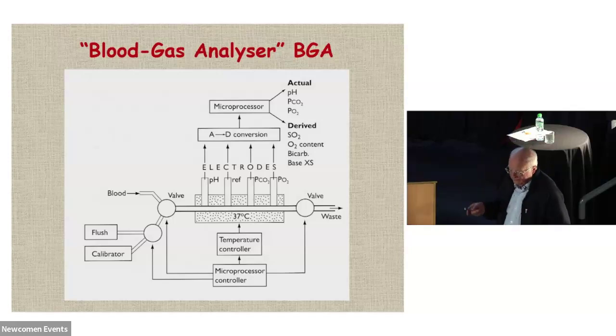So now moving from the gases to looking at blood. Initially, the blood, as far as plasma is concerned, which is the liquid bit rather than the white cells, the red blood cells. So these machines are not connected to the patient. You take a little sample of blood out of the patient in a syringe with heparin in it, so it doesn't clot in the syringe or clot in the machine. And you squirt about a couple of hundred microliters of blood, you can do it with nowadays, through this valve here. This would be to calibrate it or to flush it between patients.